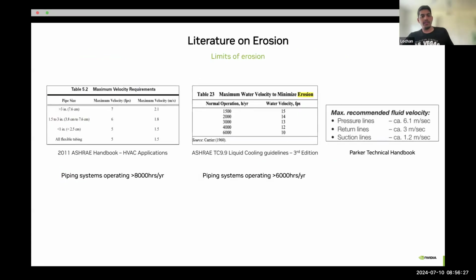So, currently, from the 2011 ASHRAE Handbook of HVAC Applications, for the flexible tubing, it was given as 1.5 meters per second in a scenario where the operation of data center loops is more than 8,000 hours per year. So this was the velocity limit which we found, 1.5 meters per second, and initially that was our main point of reference. And looking into some other guidelines from ASHRAE, the TC 9.9 Liquid Cooling Guidelines, third edition, it was mentioned we can go around 3 meters per second.